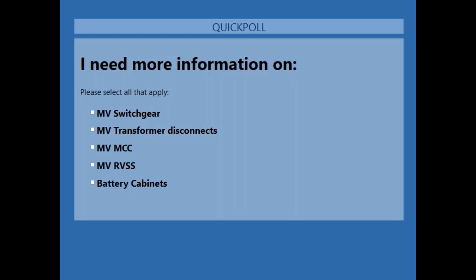Hey, Mike, this is Adam. For one, you can do it fused or non-fused, so you can also get the fuse protection feature built into it. But I do believe that HVLCC mechanism is a little bit more limited from a kA standpoint than a traditional fuse disconnect switch. I can't remember if it's 31 and a half or 40. Yeah, so it is limited compared to an air brake switch in terms of kA. It's limited to 40 kA, up through 15 kV.